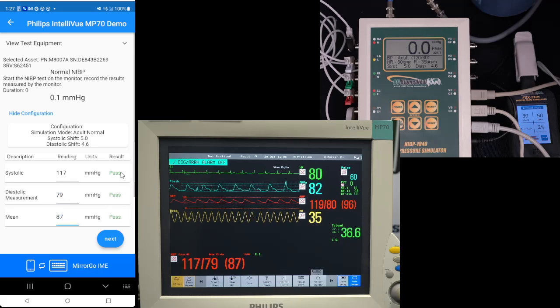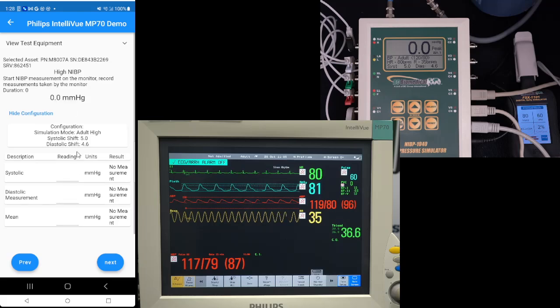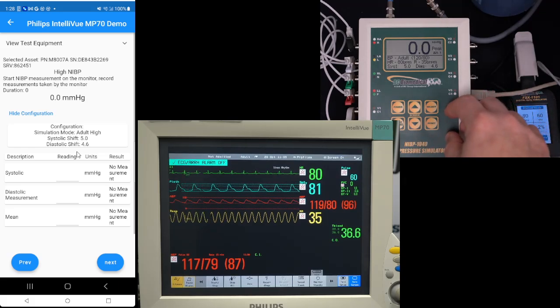Those passed. Now what you'll see as I enter the numbers, this test was already configured for me. So it already knew what measurements are expected and what the limits are, right? I would enter those limits based on the service manual for the monitor that I'm testing. And then once I enter those values, it would automatically do that for me. So we're going to go, and the next one will be adult high.